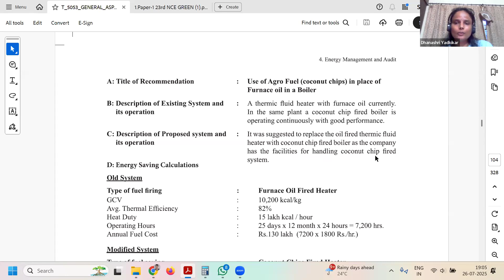So here is the specification of the old system. The type of fuel firing is a furnace oil fired heater. The gross calorific value of the furnace oil is 10,200 kilocalories per kg. Average thermal efficiency is 82%. Heat duty is 15 lakh kilocalories per hour.